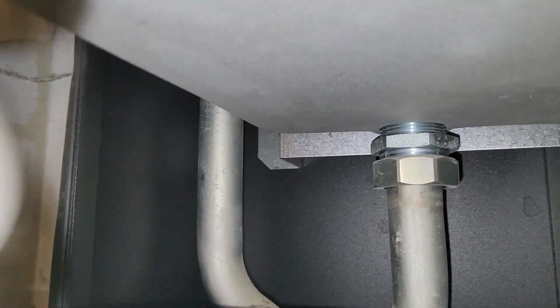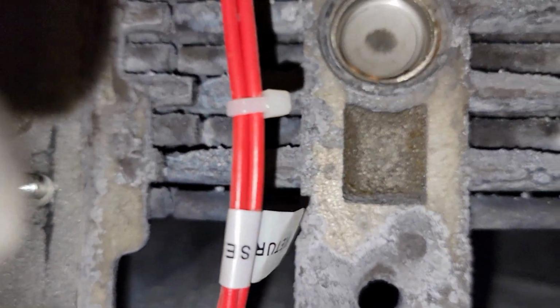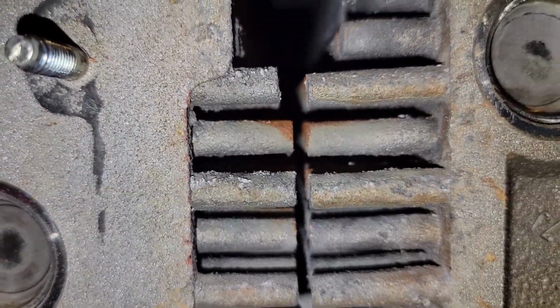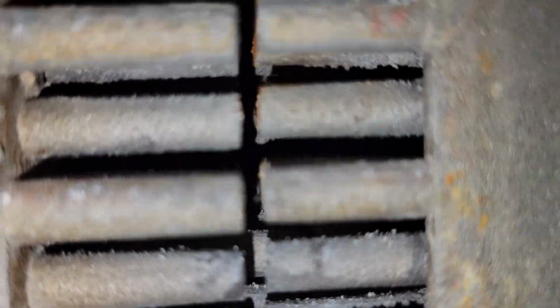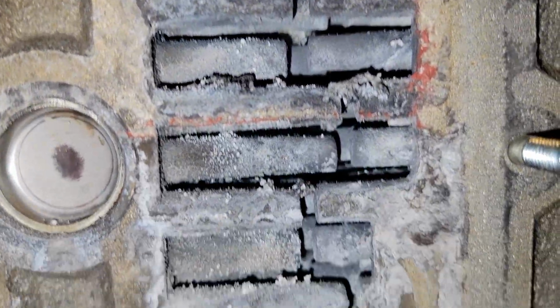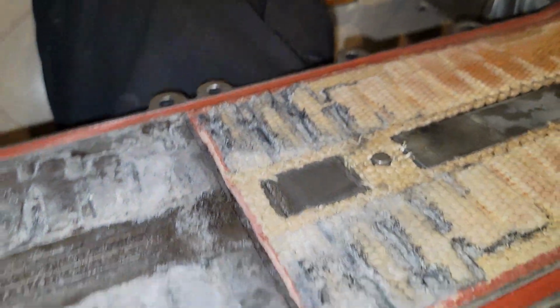Overall condition of the inside isn't spectacular. I'm going to scrape away at that bottom to make sure that there's no holes forming. It does look good from underneath, but just to be sure, I'm going to be cleaning out all of these fins, which are terribly, terribly dirty. It's shocking how dirty they are. This has clearly not been serviced in a very, very long time, if ever.